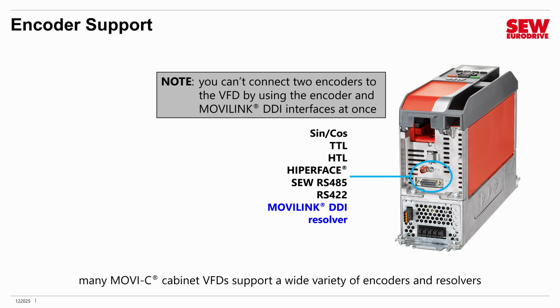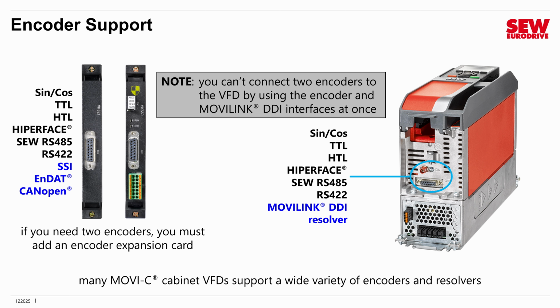What if you do need two encoders, however? Is there a solution? Of course there is. You put an expansion card in the VFD and add a second encoder interface. We offer a number of expansion cards, and you can see they support similar standards to the built-in encoder interface, but there are a few differences which I've called out in blue so you can notice them.